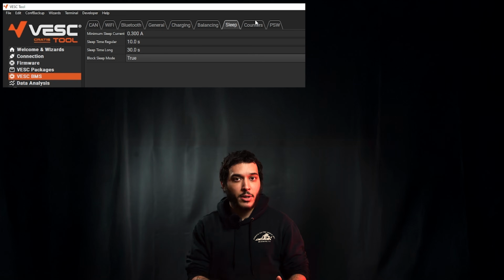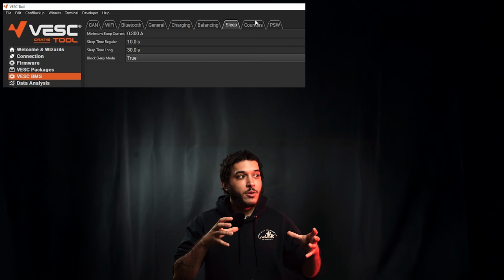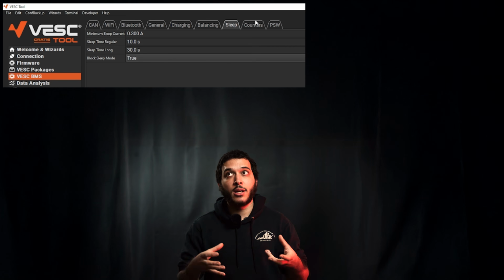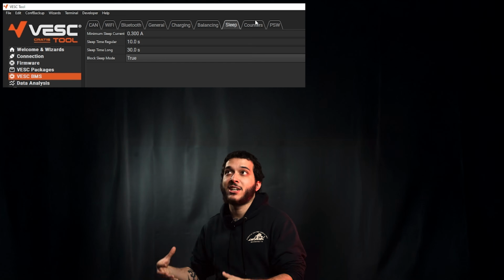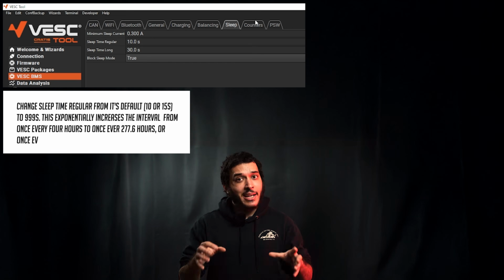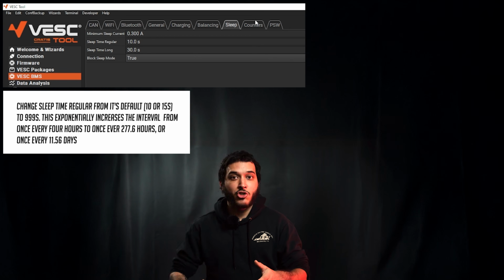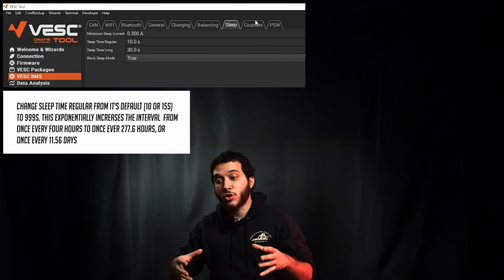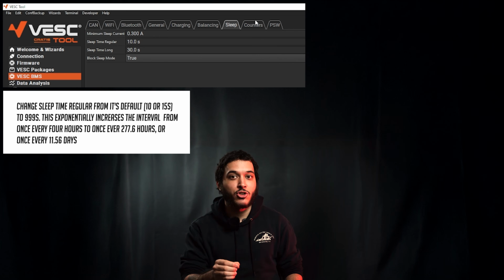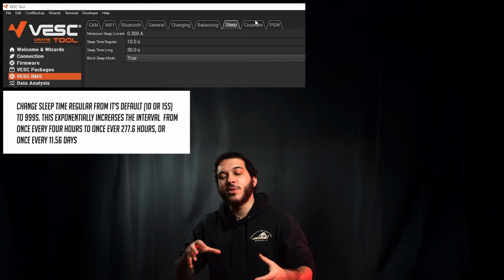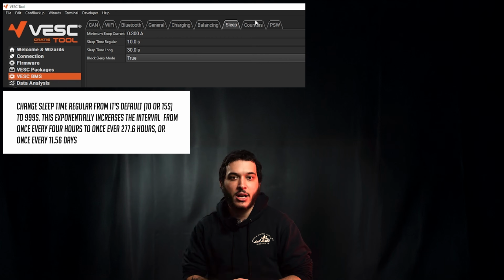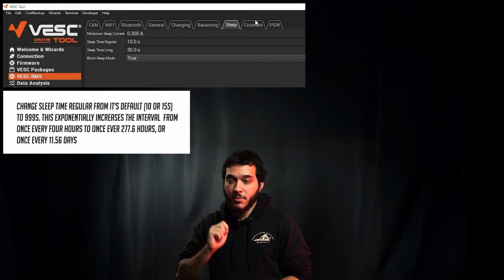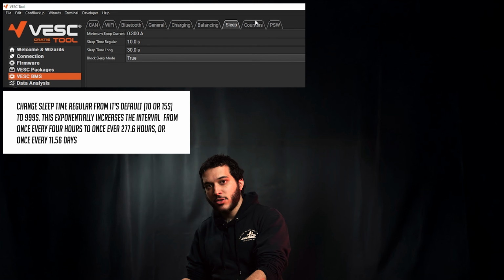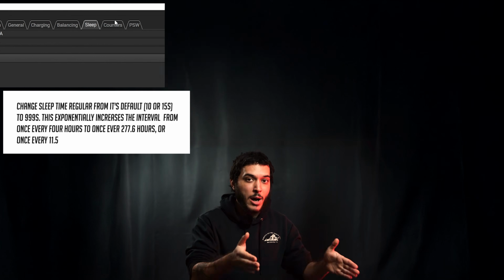If this double beep is annoying you, you can change this from its default setting of 15 seconds to a larger number, like 999 seconds. Now that light system check is happening every 999 seconds. And after 1,000 of those 999 second interval checks, it'll do that longer, deeper system check, and you'll hear that double beep. But instead of beeping every 4 hours, it'll beep once every 12 days. Much easier on the ears.